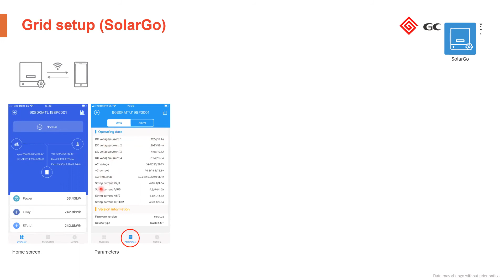This is something that we want to do now because we are doing the commissioning, the first commissioning of the inverter, right? So in system parameters, we can set up the time. In grid connection parameters, we have to select the country. In this case, as I mentioned, it was in Spain, a real case, and the selection of the grid. There is a second screen, and we can select the type of grid with or without neutral, right? And then it has been finished.